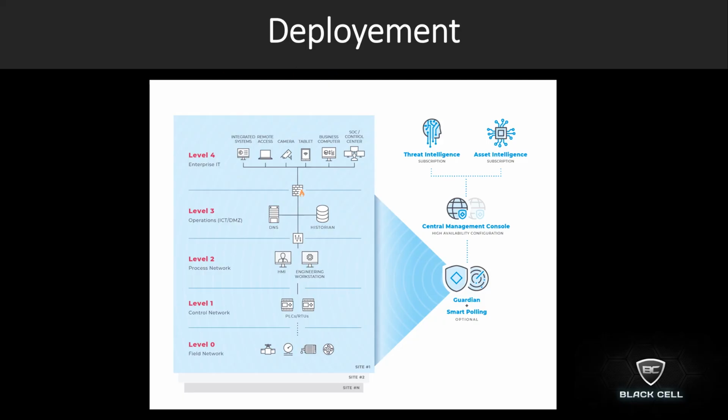The Guardian goes through a learning process after commissioning. It processes and analyzes communications using artificial intelligence. It will learn what ICS devices communicate, what codes they control, with whom they communicate, and how they operate. The learning process can be automatic or manual, meaning that operators can mark operational processes, thus speeding up and supporting the learning process. Since the Guardian interprets ICS protocols and communications and records operational processes, it is also able to respond to changes in programming codes and devices, detect changes and deviations, and send alerts about unusual variables and codes.